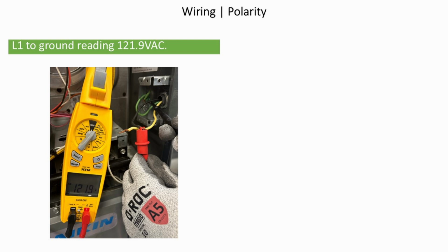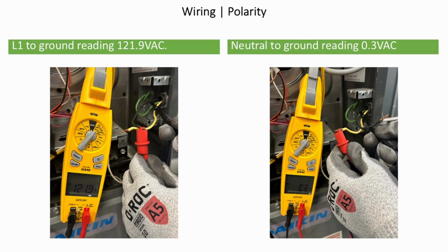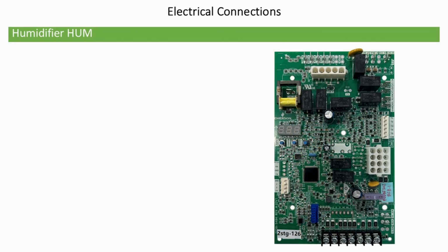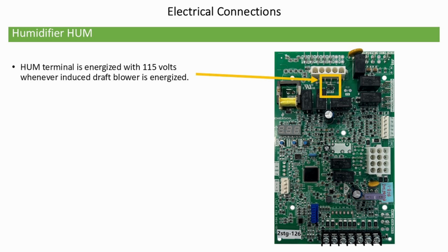Wiring, polarity. L1 to ground should be approximately 120 volts AC. Neutral to ground should be a maximum of 0.3 volts AC. Electrical connections. Humidifier. The HUM terminal is energized with 115 volts AC whenever the induced draft blower is energized. This terminal can also provide 120 volts AC to a humidifier transformer for 24-volt applications.